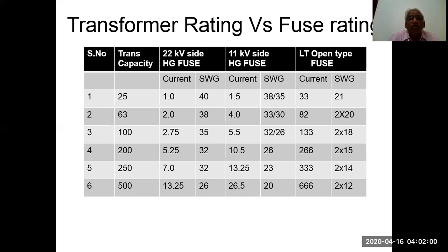On the left side we have given the transformer capacity: 25, 63, 100, 200, 250 and 500. To the right, the next column is the current rating. The next column is the standard wire gauge, which you have to use. Kindly follow this. Read it two or three times and follow it. This will help you in saving the transformer without any damage.